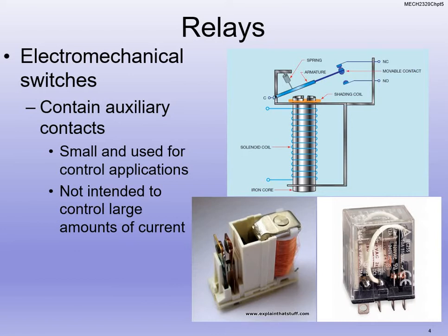It's the exact opposite if we have a normally open relay — the magnetic field closes it. We use auxiliary contacts in small control applications because they cannot handle large amounts of current. These are our electromechanical switches. Before PLCs, you'd have a whole control cabinet wired up with a bunch of electromechanical relays, and that would be the logic as these relays open and close. But these small ones are used for just smaller control applications — no high voltage, because it will blow them.